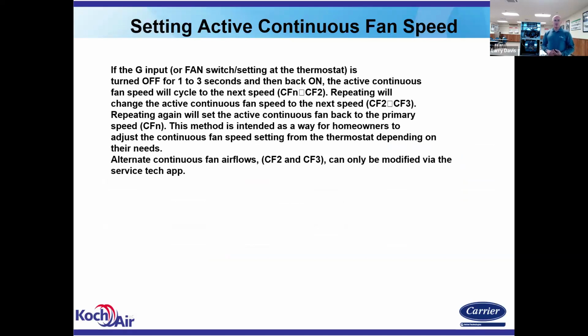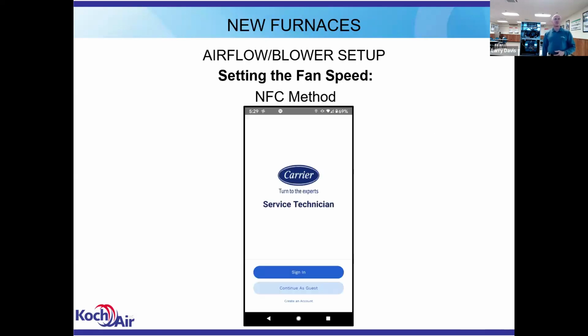On the mid tier, or the premium tier, if you're not using the communicating wall control, you can toggle the fan switch off and on at the thermostat, and it'll change that constant fan speed. You have like 3 different ones. So sometimes you've been out on a job, you're doing a startup, and you've noticed that the fan, which I have on just a G call, sounds a little different than it did. Well, toggle it off and back on within 3 seconds, and it's going to sound different again. So that homeowner can change that, but you want to let them know so that they don't call you thinking there's something wrong with the furnace.